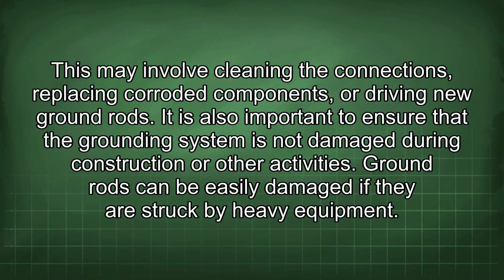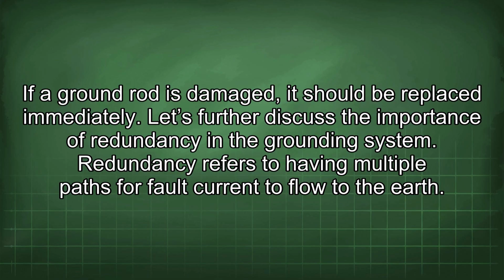It is also important to ensure that the grounding system is not damaged during construction or other activities. Ground rods can be easily damaged if they are struck by heavy equipment. If a ground rod is damaged, it should be replaced immediately.